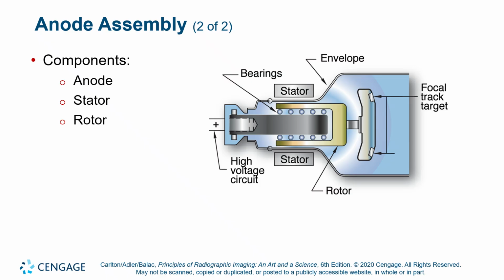Okay? So now your molybdenum wheel and your graphite is heated up. The graphite will give that heat back to the molybdenum. The molybdenum connects directly to the anode stem, which is also made out of molybdenum. Now, most of the time that is bolted on to the metal anode wheel. It's a bolt and screw thread assembly. And then the molybdenum stem is fused directly to the armature of the rotor, which is the outer shell or the outer cup of the rotor. The outer cup of the rotor is typically made out of copper such that it can rotate.